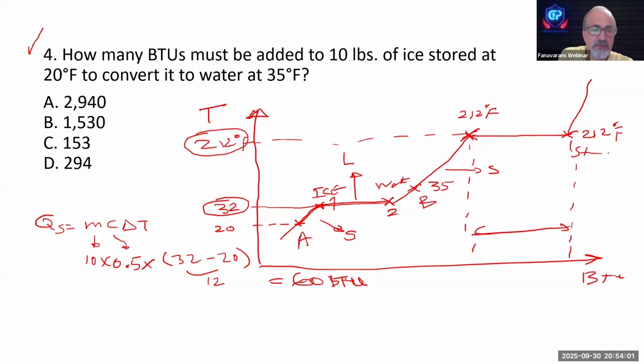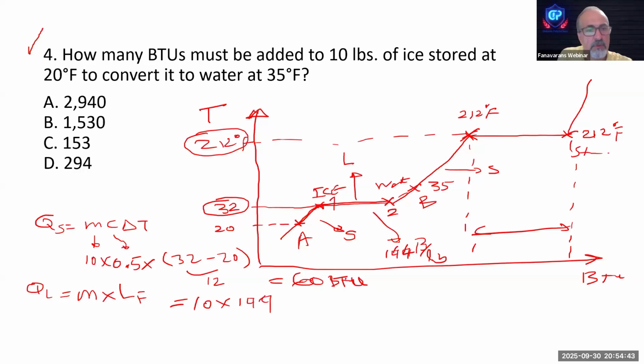The next part is the latent heat. You need to calculate from point A to B. So sensible heat is done. Latent heat from 1 to 2, the QL is the pound of the water, M times latent heat of fusion, LF. Latent heat of fusion of water is 144 BTU per pound. So if you have 10 pounds of water, 10 times 144, this is 4, not 9, guys. And it's going to be 1,440.